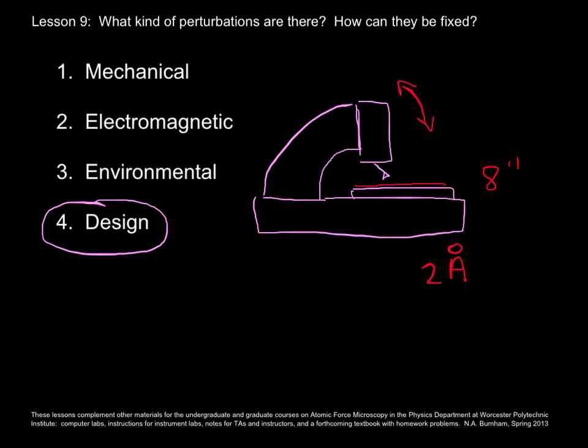And in addition to mechanical design, also be wary of what you're buying when you buy an AFM in terms of the electrical design. Some manufacturers will choose an electrical frequency range to be narrow as a way of limiting noise. But you might require certain measurements to be done at high frequencies that require a higher range of frequencies to be collected.